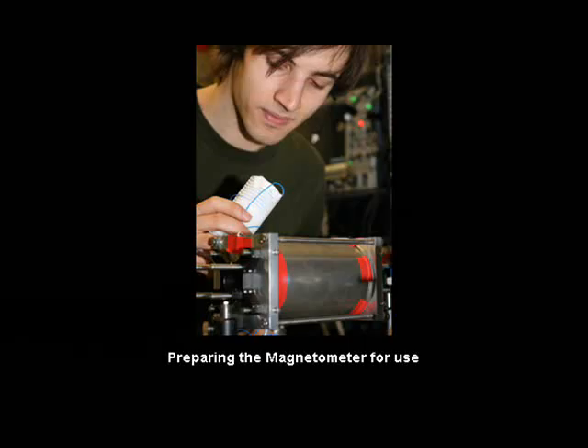What we're looking for is a change in the gas introduced by a magnetic field that we apply. Gases — especially rubidium in this case — are particularly sensitive to magnetic fields. This sensor is housed in several layers of magnetic shielding, which enable us to reduce the Earth's field by about a billion fold. We then pipe the signal that we want into this device using a series of coils that cancels background noise and keeps only the signal that you're interested in. By putting those two together, we've developed a relatively small, essentially handheld probe that could be used to detect the field.